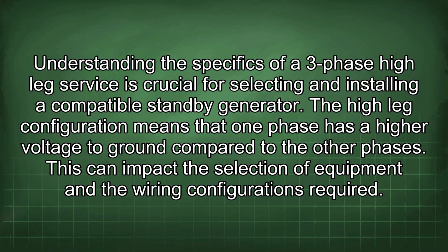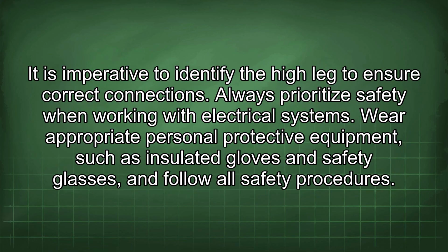Understanding the specifics of a three-phase high-leg service is crucial for selecting and installing a compatible standby generator. The high-leg configuration means that one phase has a higher voltage to ground compared to the other phases. This can impact the selection of equipment and the wiring configurations required. It is imperative to identify the high leg to ensure correct connections.